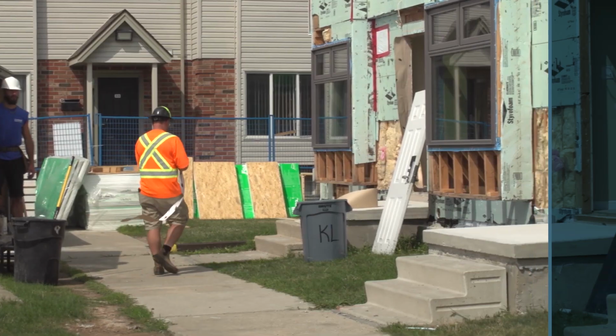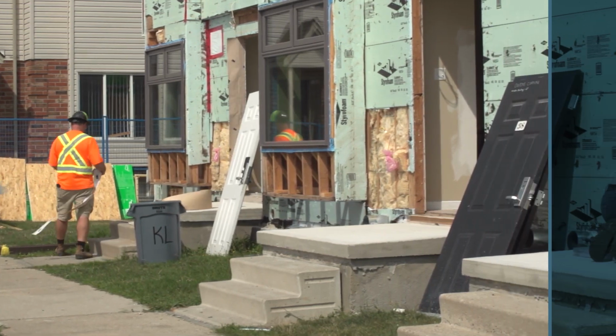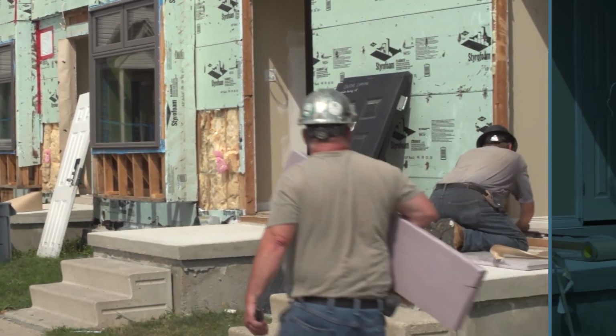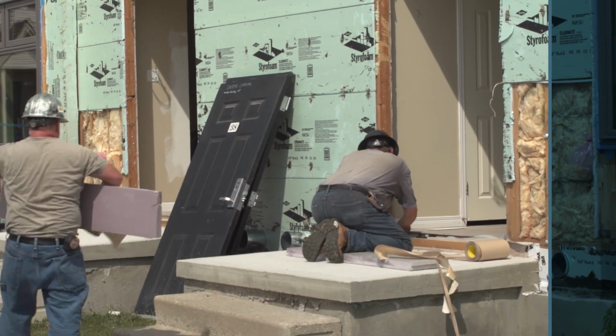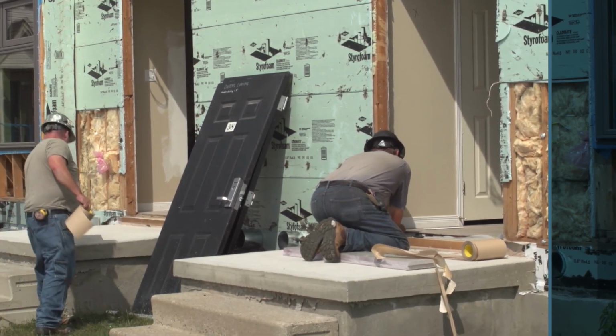Decide what efficiency upgrades you're going to prioritize, and with the end goal in mind. Then chip away methodically at the envelope upgrade measure by measure until the building matches the target. I cannot emphasize enough the importance of first doing the envelope upgrades. This will enable you to install a much smaller heat pump and backup heating system than would otherwise be needed. In the long run, this approach will require less capital, have a quicker payback, and save more energy and GHG emissions over the lifetime of the system.